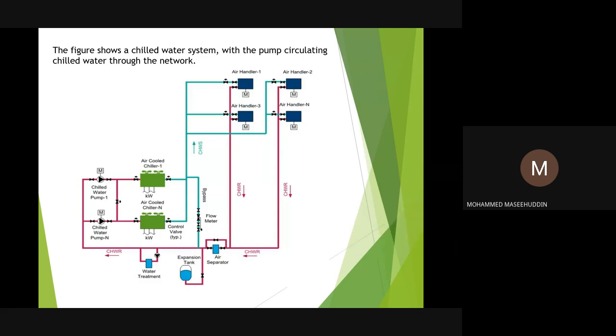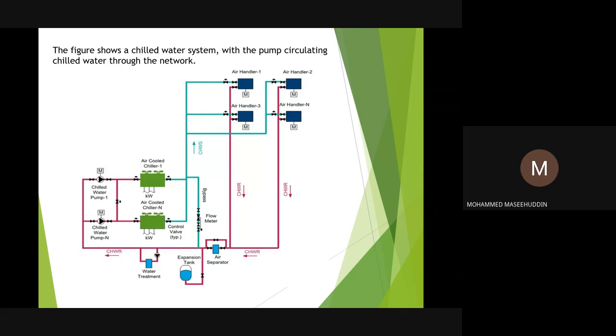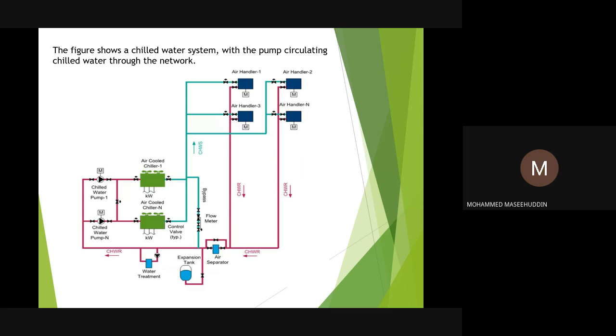So chiller 1 is pumping the chill water to air handling units 1 and 3. And the second pump, chill water pump N, is pumping the chill water to air handling unit 2 and air handling unit N. Similarly, the warm water coming out from the buildings is returned on the return line, CHWR, to both the chillers respectively. In the circuit there are also an air separator, expansion tank, and water treatment. Water treatment is basically a dosing unit. And the expansion tank, as we discussed in our last slide, is used in the pressurization unit as well.